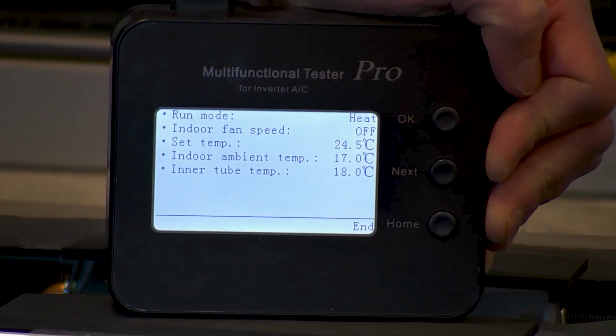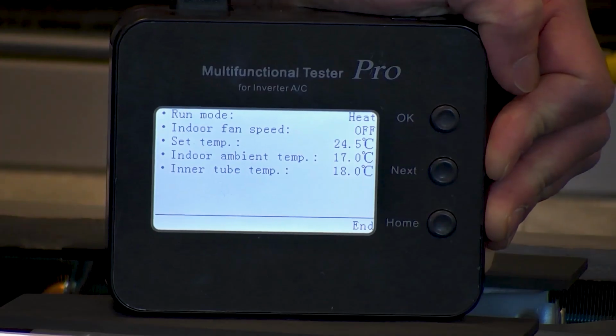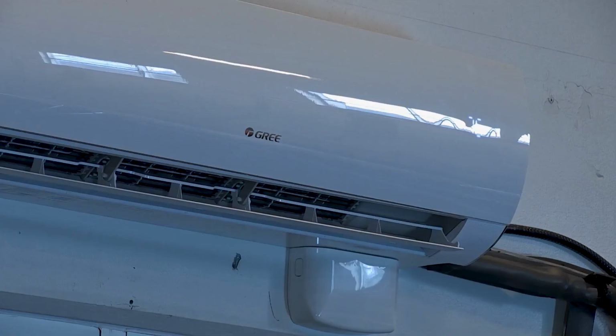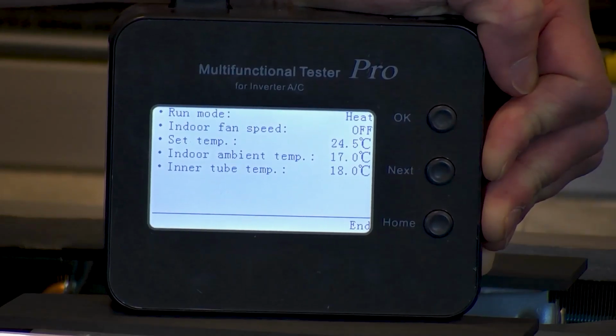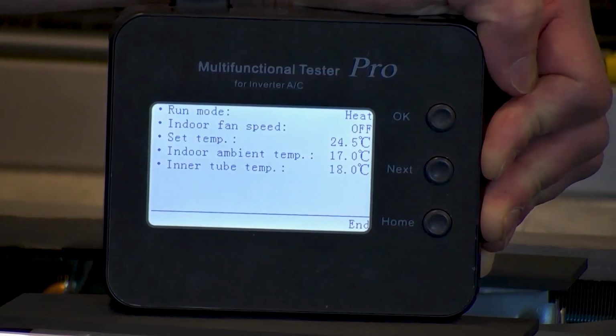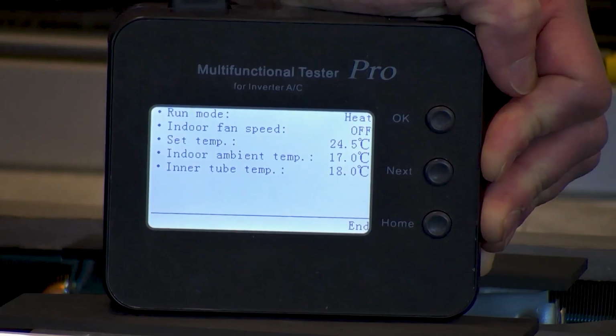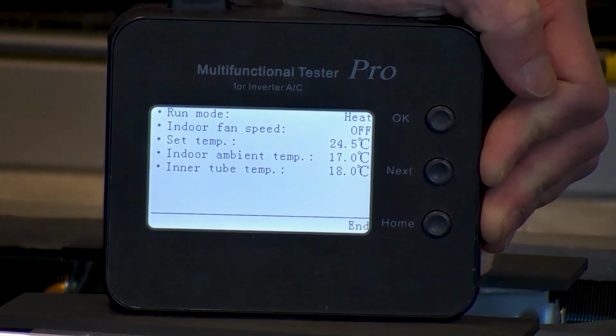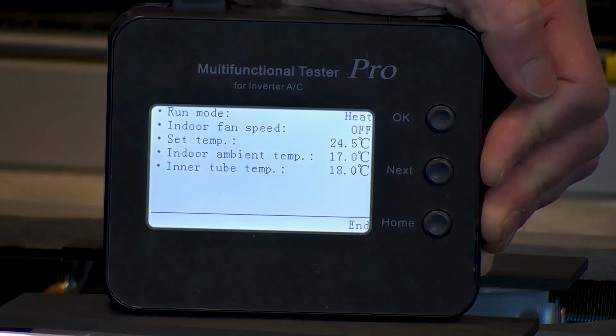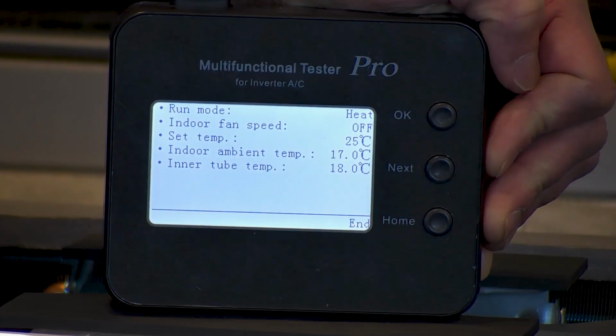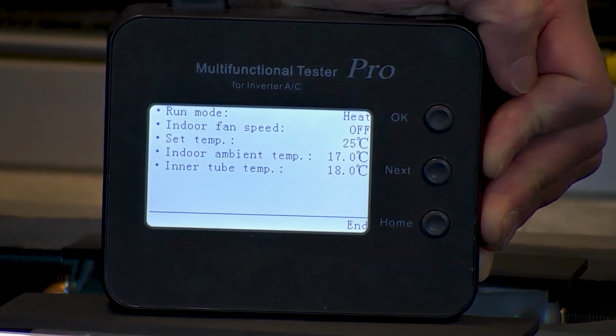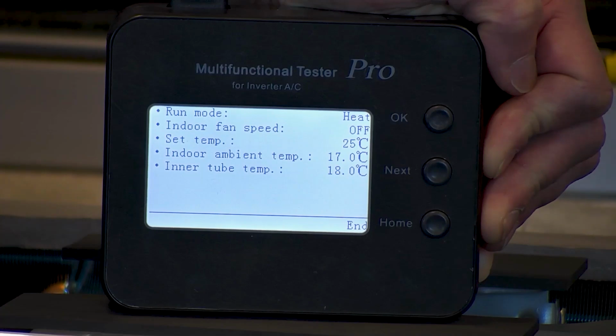So now it's giving indoor fan speed, which is set to off. Set temperature, 24.5 degrees Celsius. Indoor ambient temperature, 17 degrees Celsius. And inner tube temp, 18 degrees Celsius, which would be your indoor coil sensor. I'm waiting to see if it'll turn the fan on. Let me put it on fan mode.